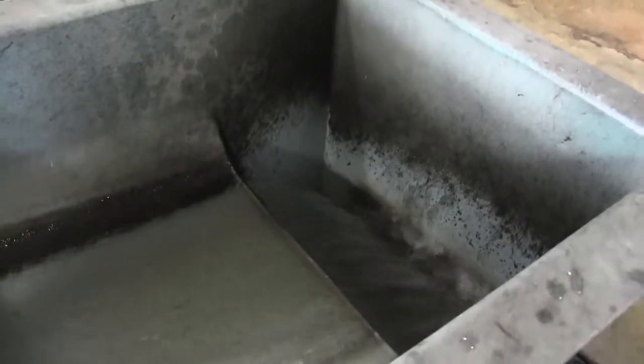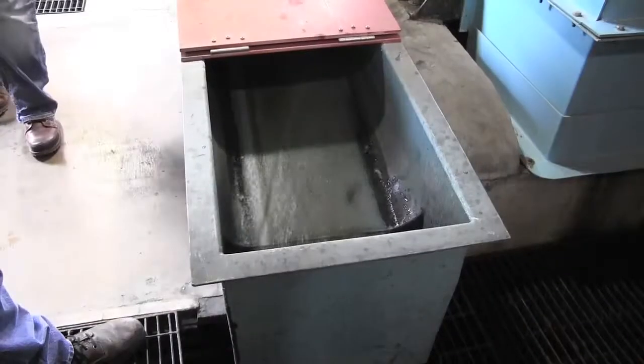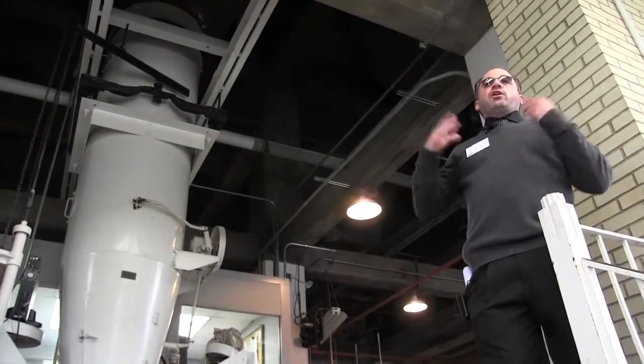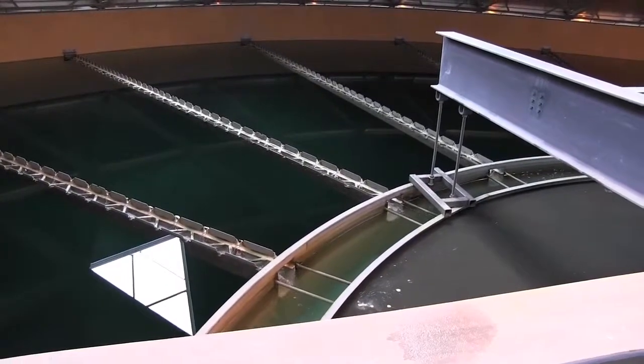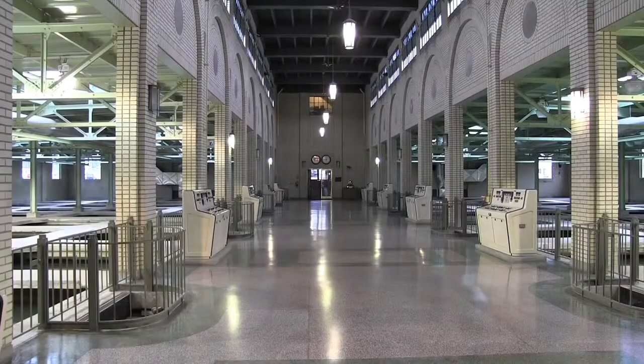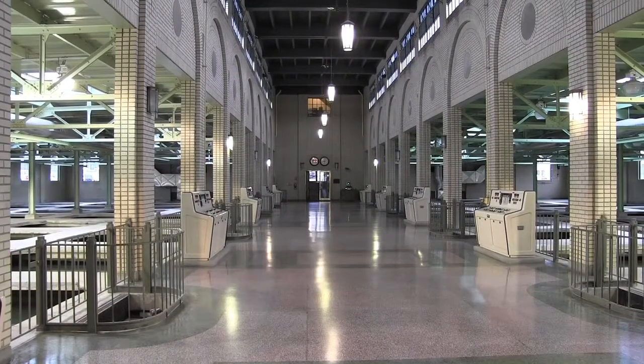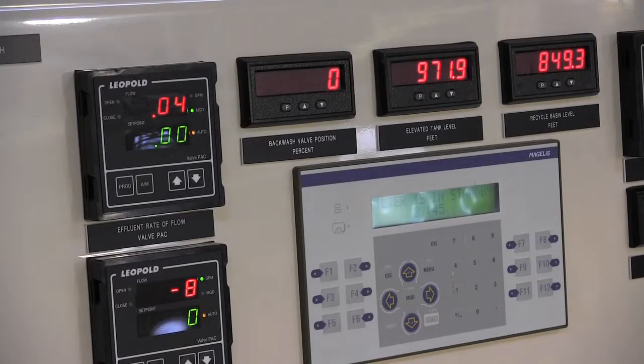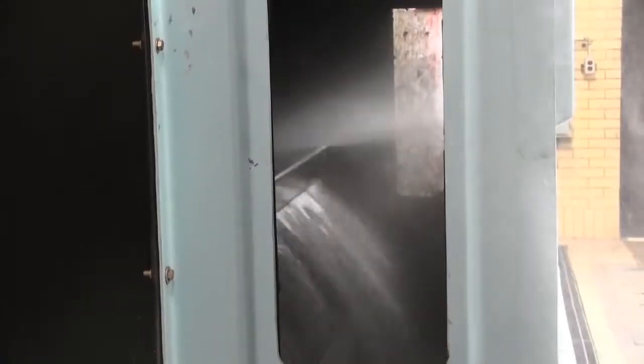The water is tremendously different and extremely better. I've been here for 30 years. And the biggest change was due to Tony Vigorito having the courage to totally change the type of coagulant chemical that we use. We've also lowered the amount of lime that we would put in the water. Our hardness under the old process would probably be in the 80s or 90s milligrams per liter. We've gotten that down into the very low 60s, so it makes the water a whole lot softer. Overall, the turbidity of the water has decreased substantially, and water quality has improved.